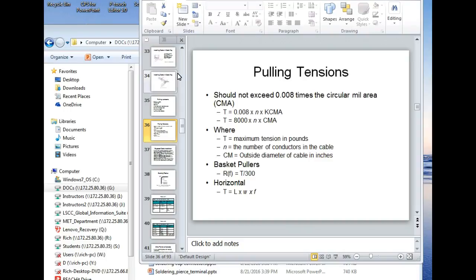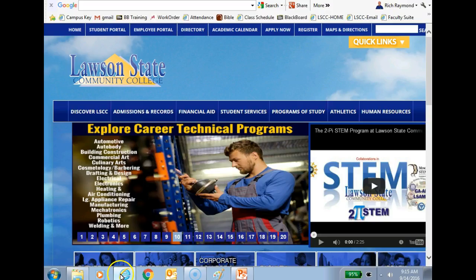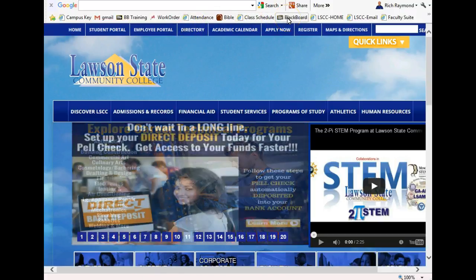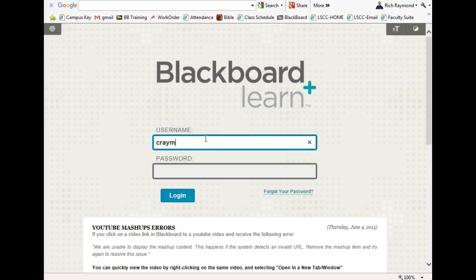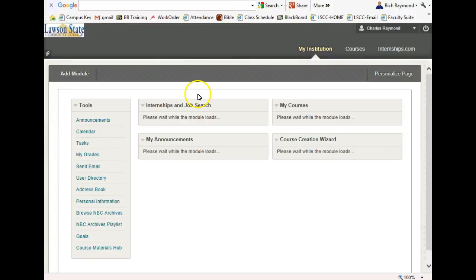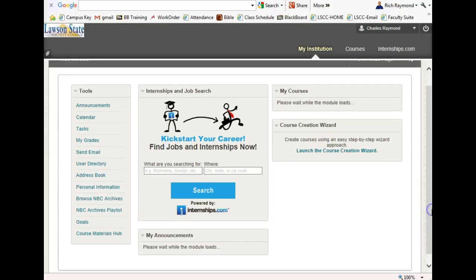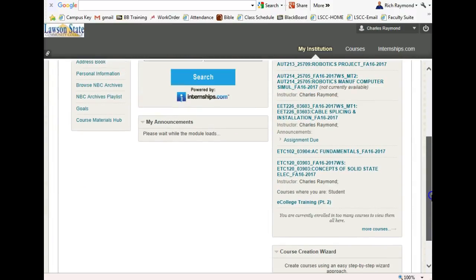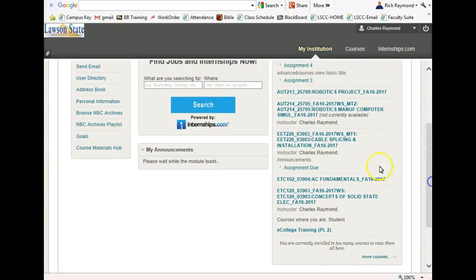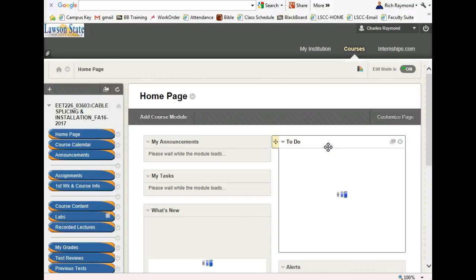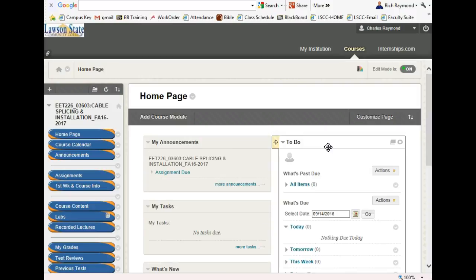Did y'all get those calculators? First of all, we need the KC mils for a 20 gauge conductor. I think I've got that up there already to help you out, another American wire gauge chart with the KC mils on it. If not, I'll add it so you won't have to calculate them every time. But how do you calculate KC mils? All you do is look up the diameter on your American wire gauge chart and square it, right?